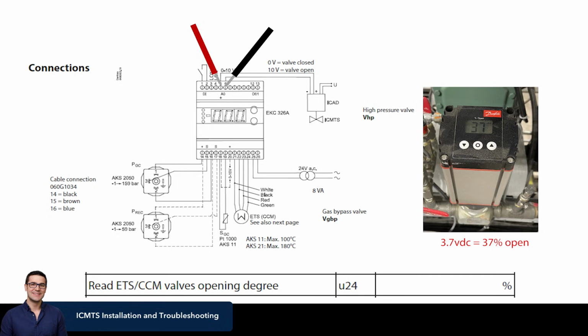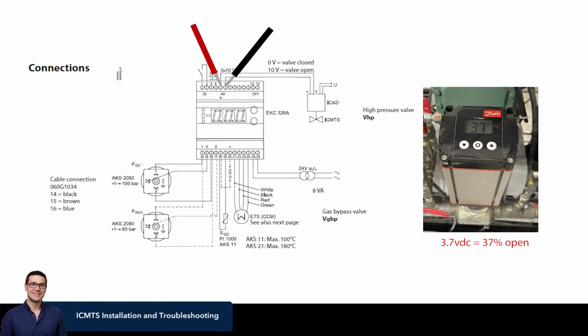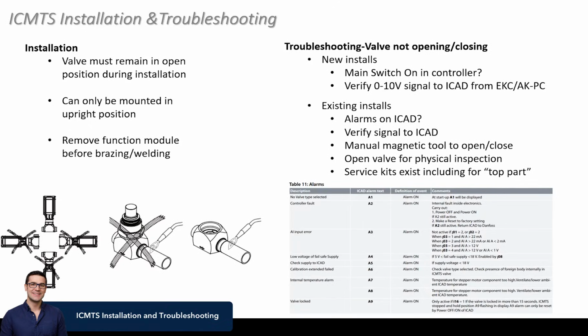But if we think the controller is shooting for a 50% opening degree at some point in time, 60, 70%, whatever it might be, when we check that parameter for opening degree, we should be able to take a meter, measure the voltage at the output of that controller or going into the iCAD, and we should be able to see a voltage that matches up with that, knowing it's a 0 to 10 range. So 50% open being 5 volts, 60% open, 6 volts, etc.